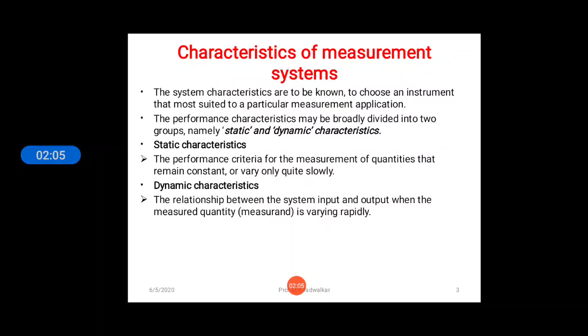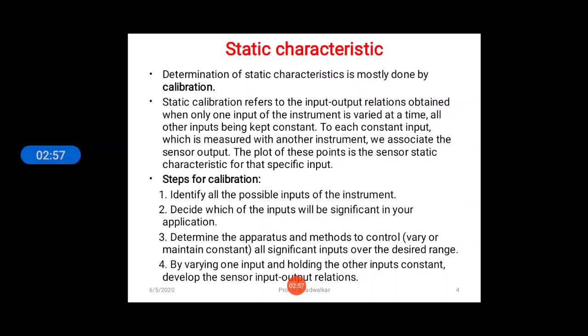Now, these static characteristics are considered here with the calibration process. The calibration process has been shown in this. In this calibration, for the static calibration especially, the input-output relationships are obtained when only one input of the instrument is varied at a time. That means, for example, when we are considering the measurement of pressure with the help of a pressure gauge, the remaining parameters like volume, temperature, all the other parameters are held constant, and when the pressure is changed, the output of that pressure gauge is determined, and the input-output relationship with this variation in only a single input, that is the pressure, will be considered.